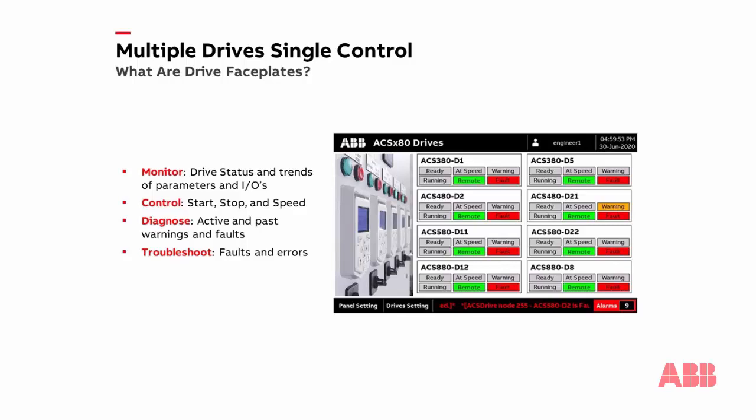The ABB drive faceplate application is simply a pre-programmed operator interface that allows for the monitoring, controlling, diagnosing, and troubleshooting of up to eight ABB ACS-compatible drives. The application takes away much of the work system integrators normally would need to create an HMI project, thus saving you time and the difficulty of an automation setup. The faceplate includes features that monitor drive status and trends of parameters and inputs and outputs, controlled start, stop, and drive speeds. They help us diagnose active and past drive warnings and faults, and can facilitate troubleshooting of many faults and errors without actually opening the drive.